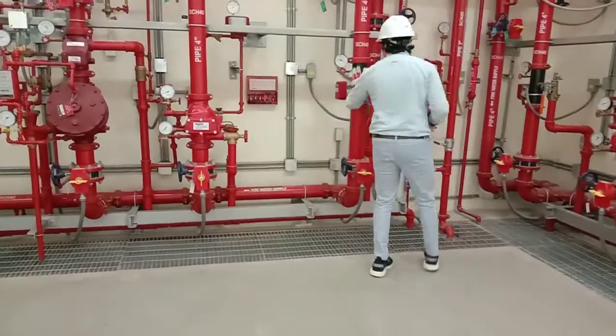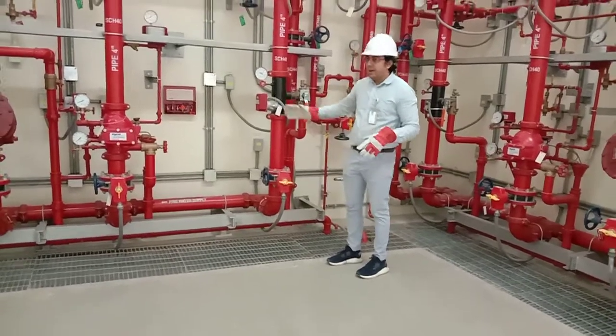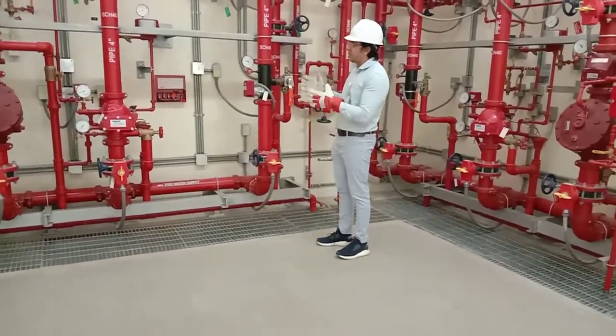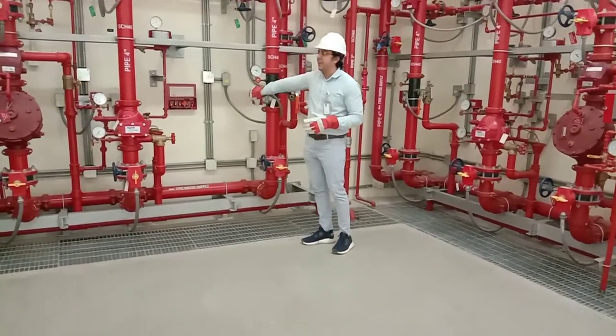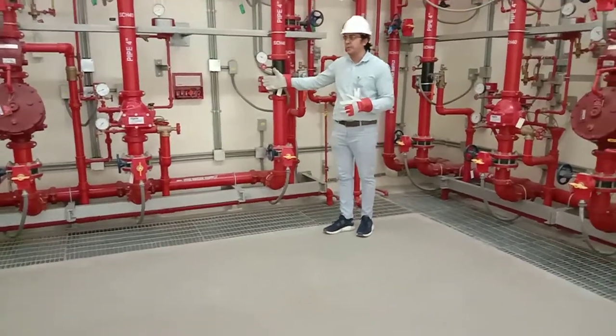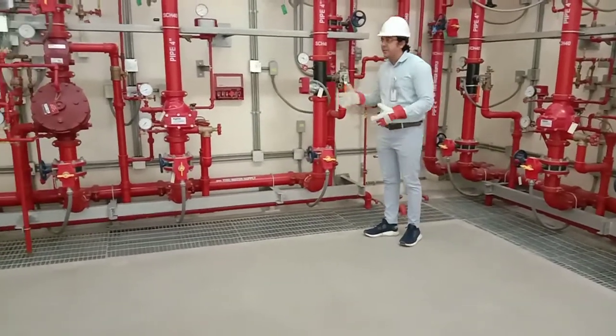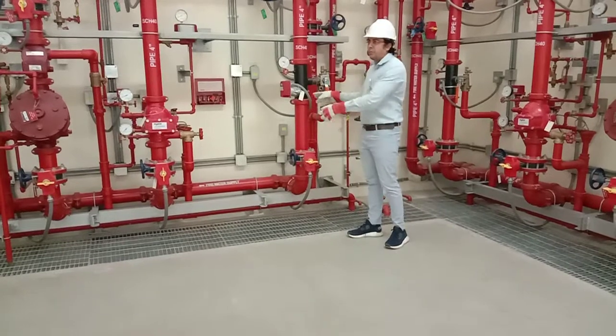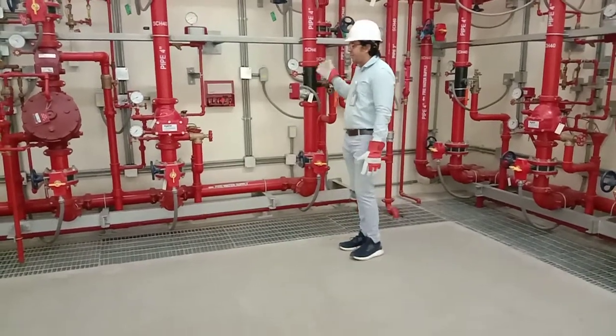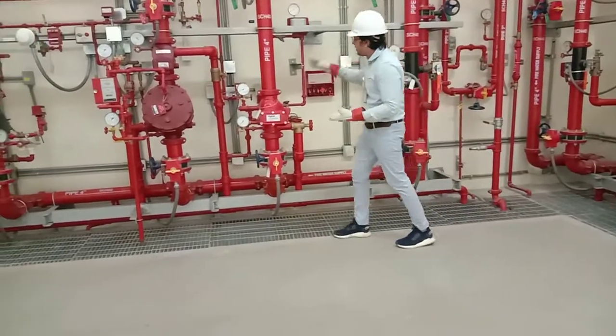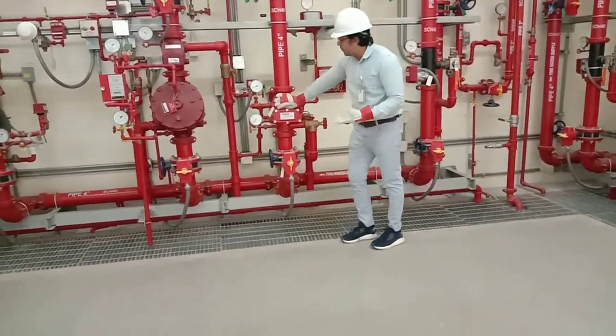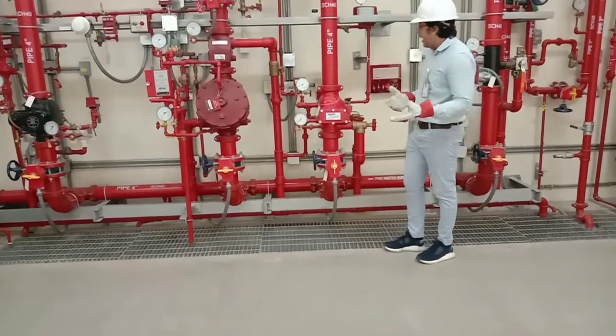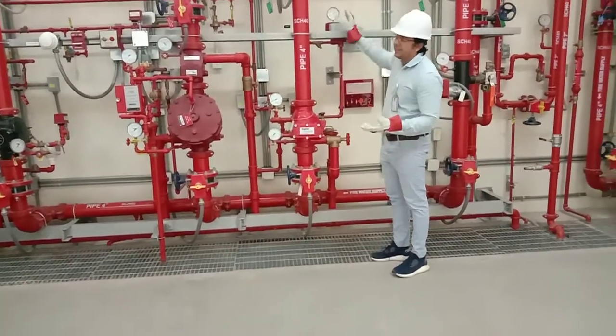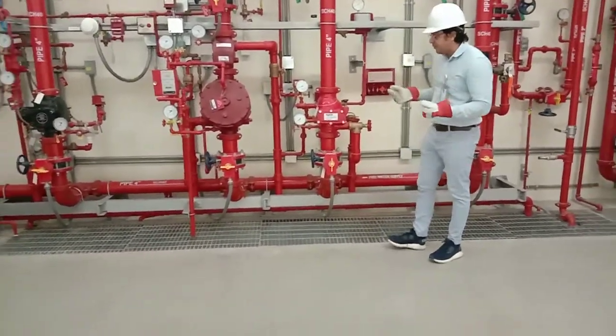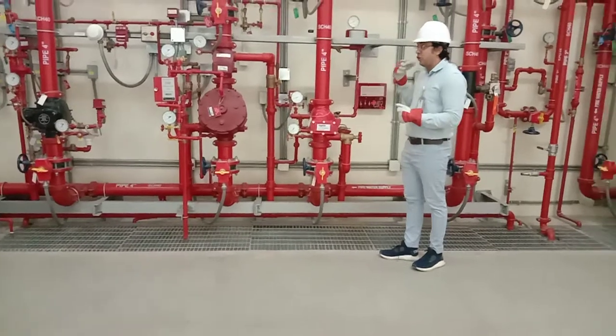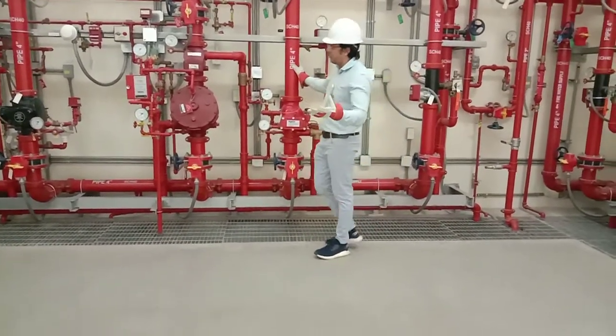Right? The easiest one, we have the wet pipe system. If you are walking around and you want to see what is the wet pipe system, you just look for the red box. If you find that red box or flow switch, it means this is a wet pipe system. And the other way, we can imagine it has the least components, right? It's much easier. There is no more equipment compared to the other kinds of systems. Looking at the dry pipe valve, right? For the dry pipe valve, you can see it is more complex than the normal one, and we have 3 gauges, right? So those indicate it's a dry pipe system. It's again more costly than the normal, and we install it only in locations where there is a chance of freezing.